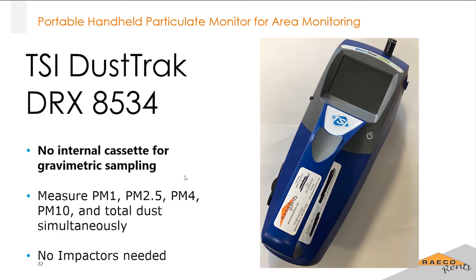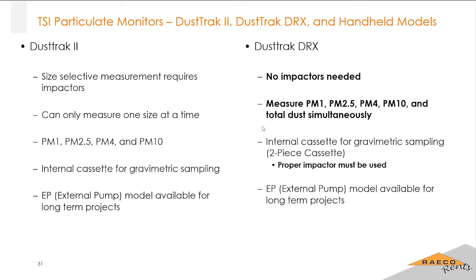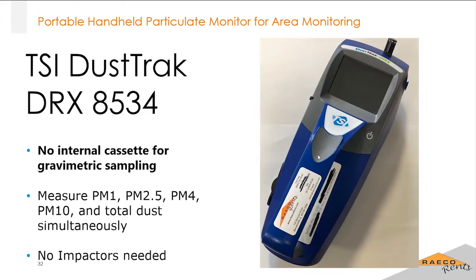It is important to note for all of these, though, that the flow rate by default is 3 liters a minute. So if you want it to perform properly and read accurately, this should be calibrated at 3 liters per minute. And when you do that calibration, this PM 2.5 impactor should be hooked up. So if you browse through a manual, you would see that. Just a little note, if you guys are going to calibrate the flow, make sure you're using that PM 2.5 impactor.